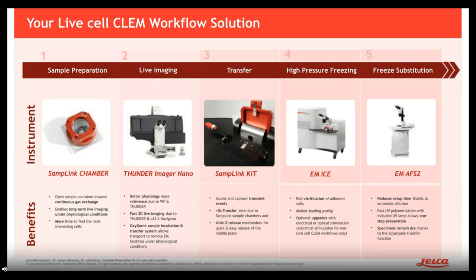After live cell imaging, we transfer the whole thing with a SampLink kit to the high-pressure freezer to enable a fast transfer to capture the event of interest. We are able to achieve a transfer in less than five seconds from imaging until the moment of high-pressure freezing. The transfer is very easy to perform in a three-step semi-automated movement. To get the best possible fixation, we use high-pressure freezing with our already established high-pressure freezer, the EM ICE, and all the benefits that come with this system.